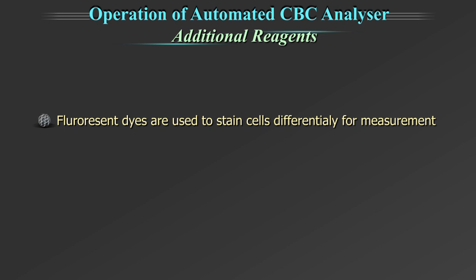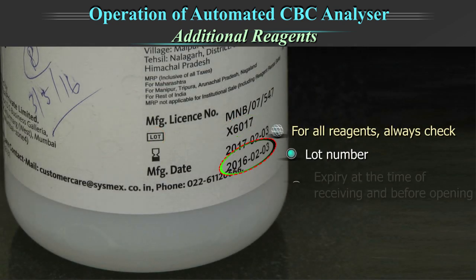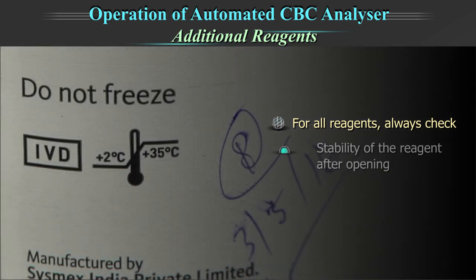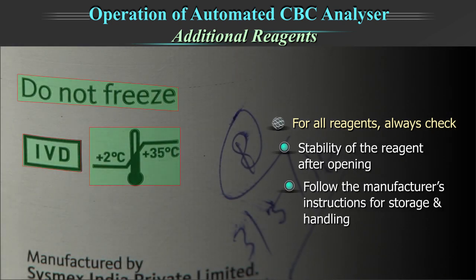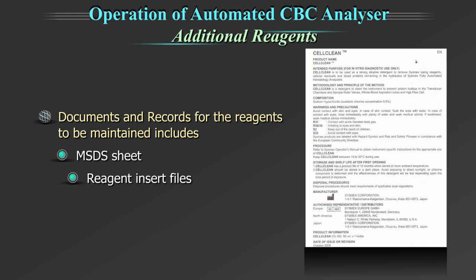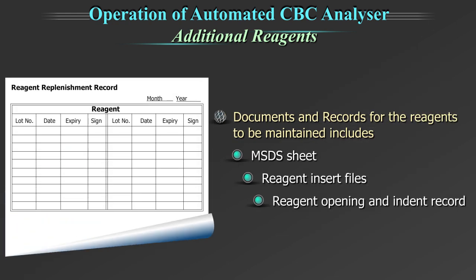In addition, 5-part analysers use additional reagents for the differential count. In some 5-part analysers, fluorescent dyes are used to stain cells differentially for measurement. In others, reagents stabilize cells for identification without fluorescent dye, as in volume conductivity scatter (VCS) technology. For all reagents, always check the lot number and expiry at the time of receiving and before opening. Note the stability of the reagent after opening. Documents and records should be maintained, including relevant MSDS sheets, reagent insert files, reagent opening records and indent records.